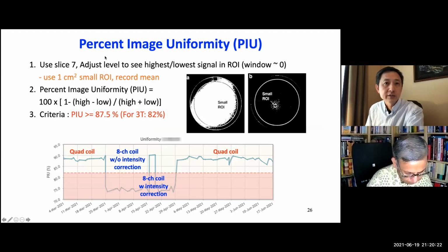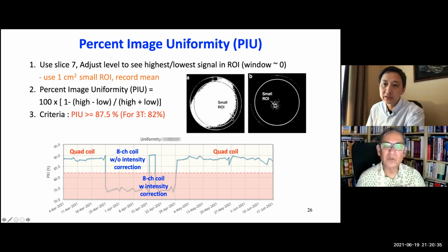And the next test is percent image uniformity. So basically, we image a uniform phantom. This is an example from slice 7 of the ACR phantom. And then look at the area with high signal and the area with low signal. So high minus low divided by high plus low, that's the non-uniformity. And uniformity is 1 minus that.